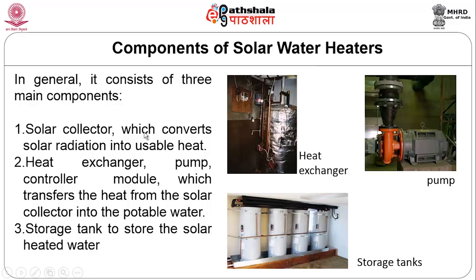Solar water heaters generally consist of three main components: a solar collector that converts solar radiation into useful heat; a heat exchanger, pump, and controller module that transfers heat from the collectors to potable water; and a storage tank to store the solar-heated water. In industrial systems, forced circulation with pumps is employed.